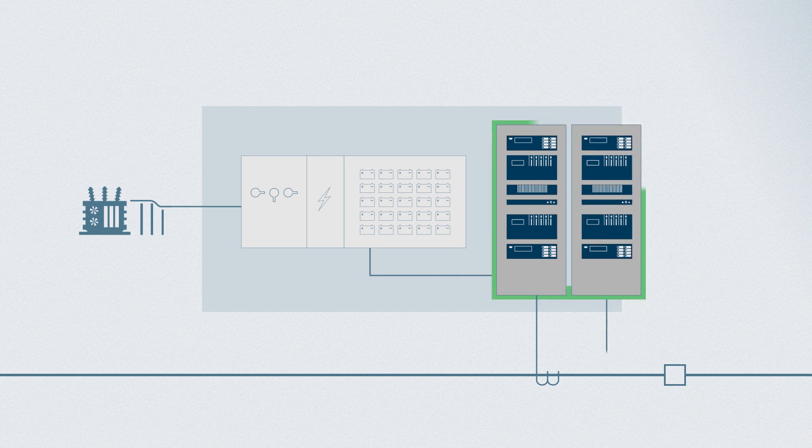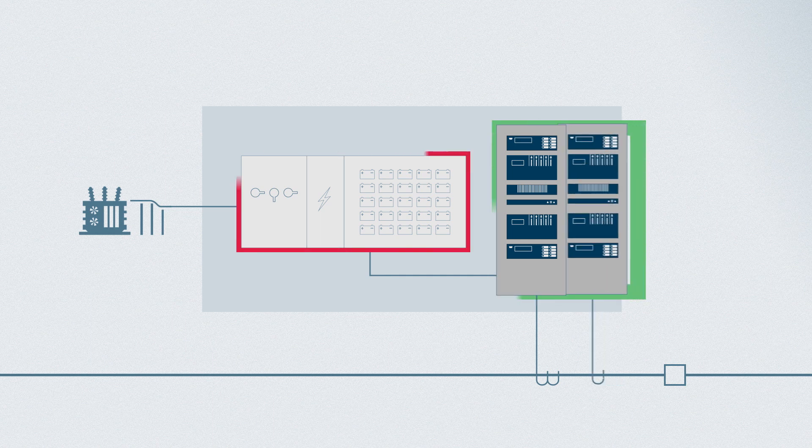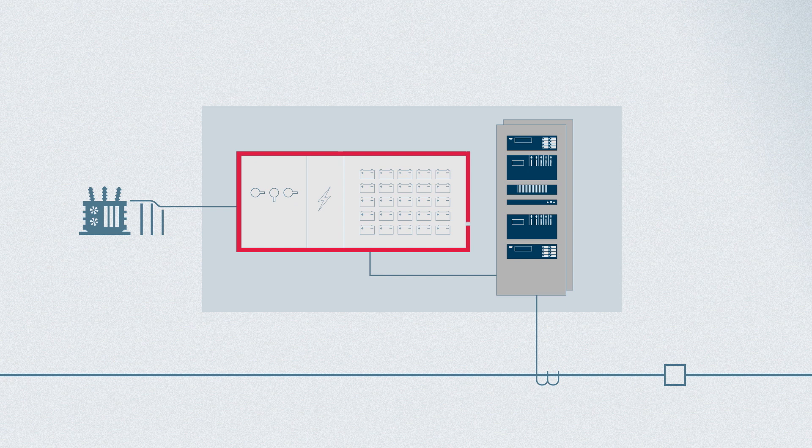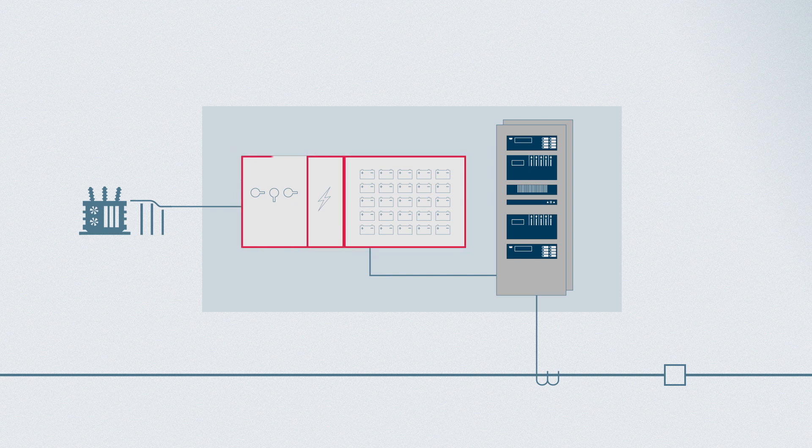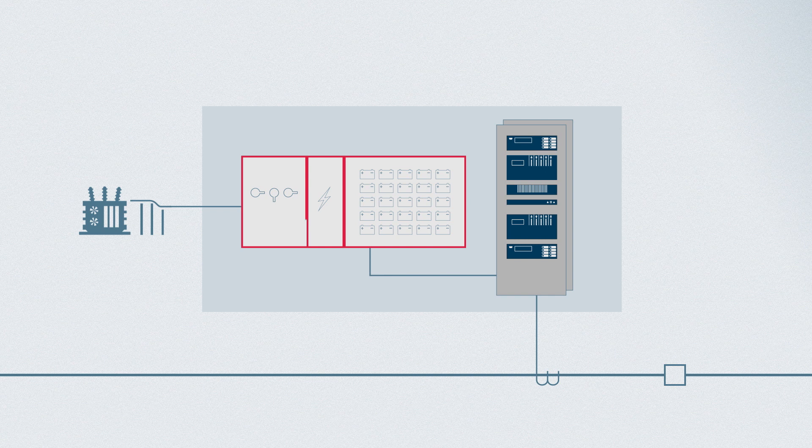In this example, the protection system is redundant, but the DC supply system is not. There is only one battery bank, one battery charger and one DC distribution panel.